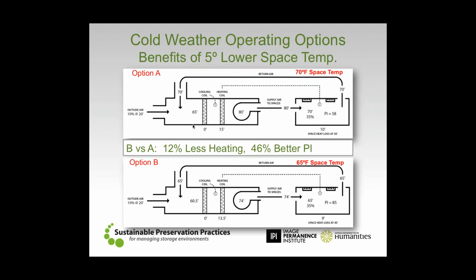So taking it from option A, which is assuming a 70-degree flatline space temp in the wintertime, well, here we are at 70 degrees and 35% RH. Now, if we go down to option B and take a look, well, what's the impact of 65 degrees? What if we drop the temperature by 5 degrees? One note I will tell you, notice that the relative humidity is the same. This particular example assumes that the humidifier is going to continue maintaining a 35% relative humidity in each of these examples. But at 65 degrees, the humidifier is going to be able to save a little bit of energy too.